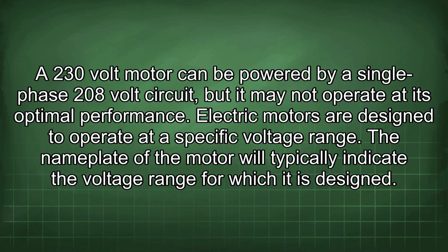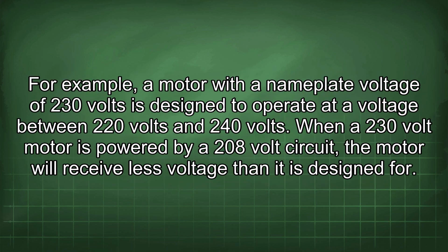A 230-volt motor can be powered by a single-phase 208-volt circuit, but it may not operate at its optimal performance. Electric motors are designed to operate at a specific voltage range. The nameplate of the motor will typically indicate the voltage range for which it is designed. For example, a motor with a nameplate voltage of 230 volts is designed to operate at a voltage between 220 volts and 240 volts. When a 230-volt motor is powered by a 208-volt circuit, the motor will receive less voltage than it is designed for.